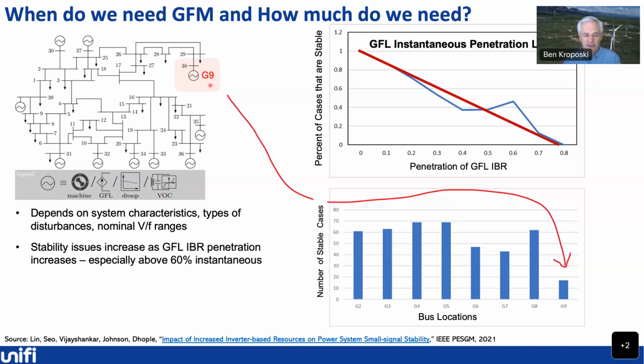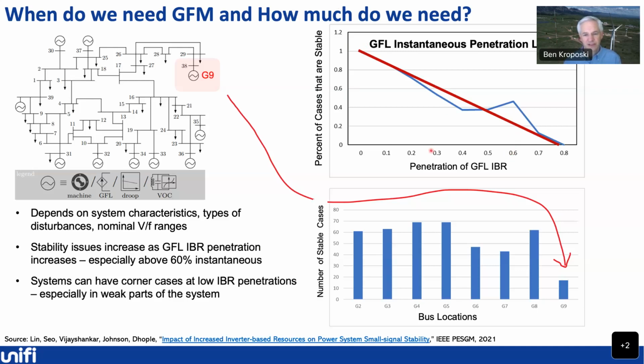Stability issues increase as you put more and more grid following inverters on here, especially once you get above 60% instantaneously. And the systems are going to have corner cases. Even at very low penetration levels, there's still some amount of cases that are unstable. Now, that's especially true when you start to move these grid following inverters and highly concentrate them in weak parts of the system. But grid forming inverters, on the other hand, they actually were able to make all cases stable and really are going to play an important role as we look to maintain overall grid stability in large-scale deployments.